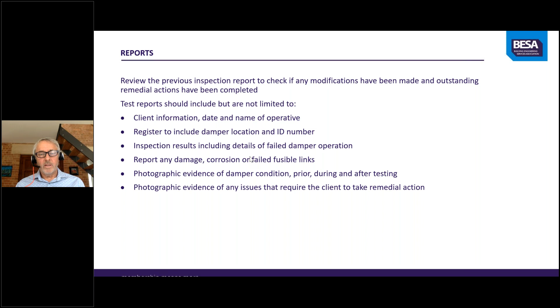Report any damage or corrosion to failed fusible links, and where lubrication is required, make sure that you use the damper manufacturer's specific instructions to follow any lubrication. If this is not available, then a PTFE lubricant should be used to minimize any adhesion of dust. Provide photographic evidence of the damper condition prior, during, and after testing, and also provide evidence of any issues that require the client to take remedial action. It's very easy these days to provide this sort of information, and it's very, very good information, obviously, to provide to the client. Next slide, please.